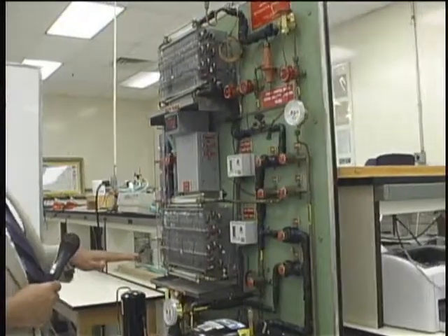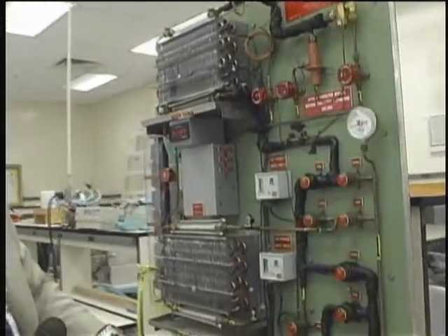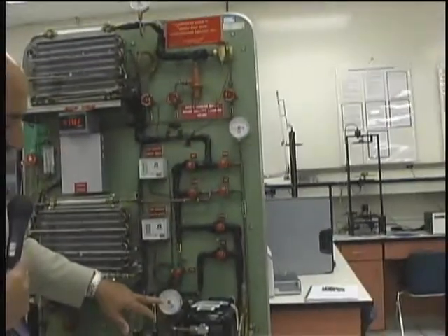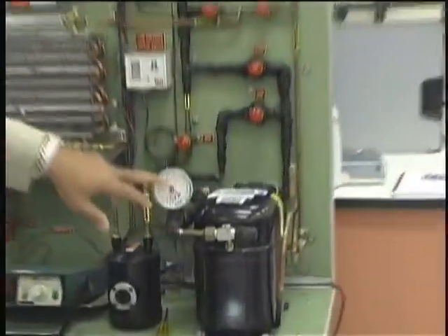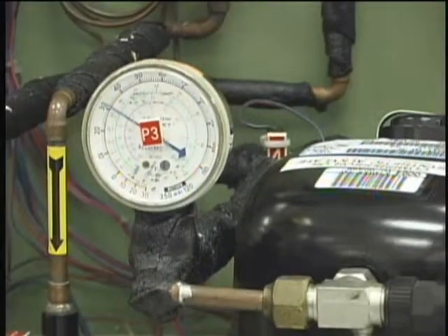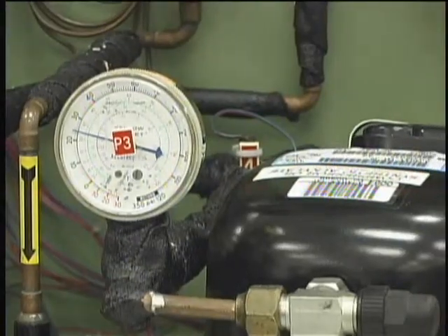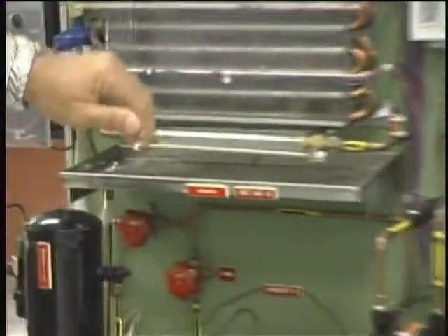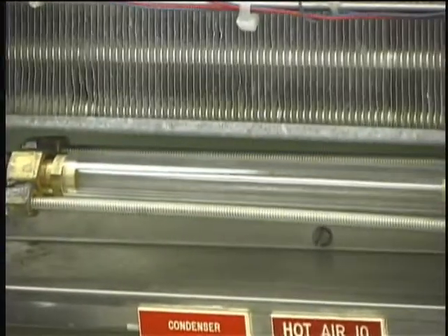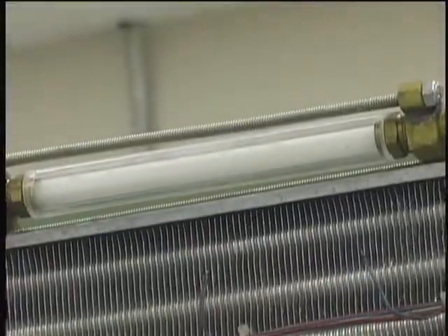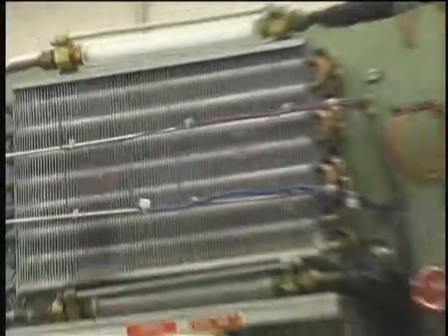You can see now that the system is a noisy system, and the pressures are kind of trying to adjust themselves. If you look at the pressure now on the compressor, you'll see the pressure on the intake is coming down. And if you look, the fluid is trying to adjust itself here to a liquid. This is vapor, and here's two-phase, you can see two-phase. So all of this is the startup process, which is very transient, and it takes a few minutes until the system settles down.